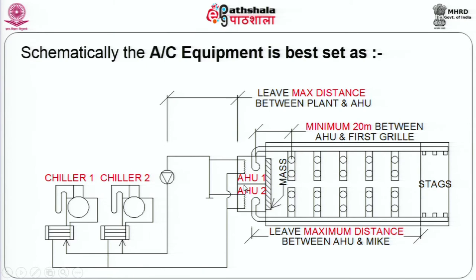It is not that this equipment is not noisy, but these links, supply air and return air, are very difficult to establish. These require, by a thumb rule, something like 1 square foot per ton of air conditioning. So, supposing you have, as we saw earlier, 100 tons of air conditioning required here, this is 50 tons, this is 50 tons. This 50 tons to be communicated to the hall and to come back will require a 50 square feet cross section. You can imagine 50 square feet is 10 feet by 5 feet, or something like 3 meters by 1.5 meters plus another 3 meters by 1.5 meters. So, if you put the air handling unit away from the roof space, you will definitely get good attenuation, but you will lose that kind of space.